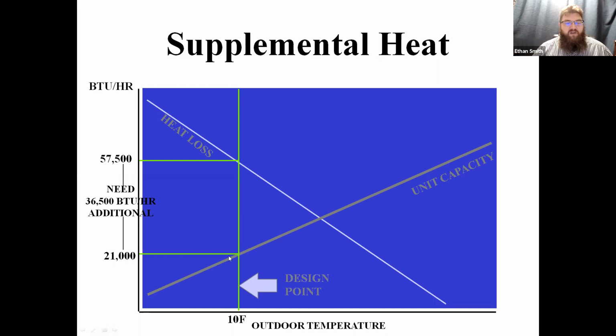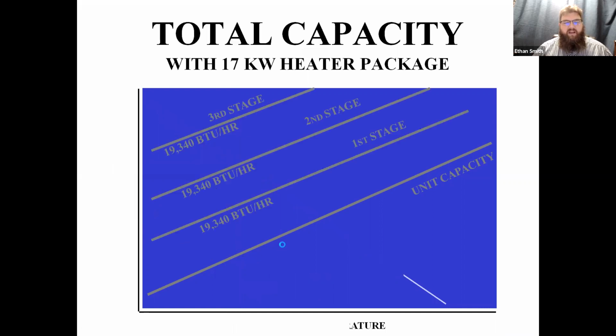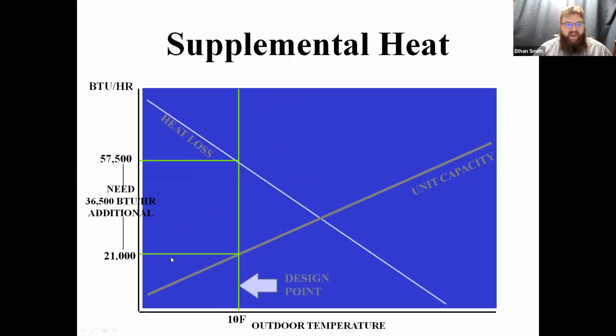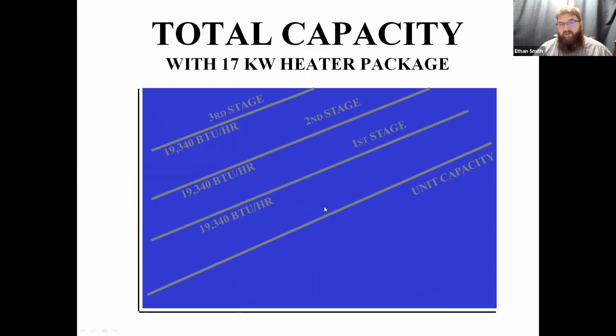And so all we do is we take the difference between our heating requirement and what we're able to deliver, and we can say, okay, I need 36,500 BTUs per hour additional to my heat pump. And then I can size electric heat off of that, okay? And knowing that, I can actually break my electric heat down into stages so that I don't have to wait until the outdoor temperature gets to 10 degrees in order to bring my electric heat on. I can actually put up to 3 stages of electric heat in there.